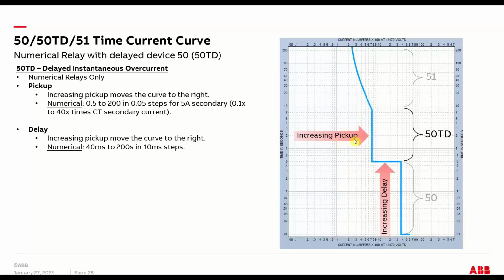And these are set with a pickup, and then a pickup or tap, and then delay. This lets you mimic some of the features that you would see in an electronic low voltage breaker, where you'd have a long time element, a short time element, and an instantaneous.